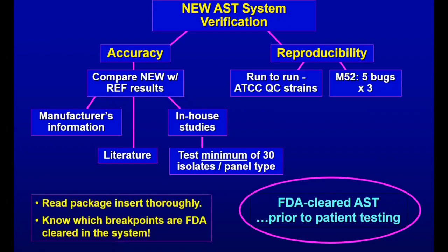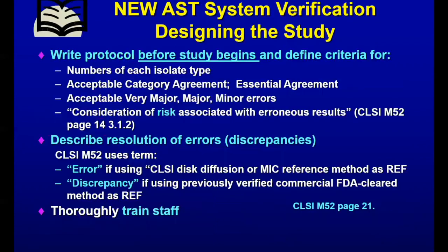triplicate. So now I think the other thing we want to talk about is the fact that it's very, very important that you're going to have to perform the testing exactly as described in the manufacturer's instructions. So you really want to look at that package insert very carefully and make sure you're compliant with all those recommendations. The other thing too is that we're going to talk about some breakpoint changes, and it's very important to know what software is on your instrument and what breakpoints are actually FDA cleared in that system.